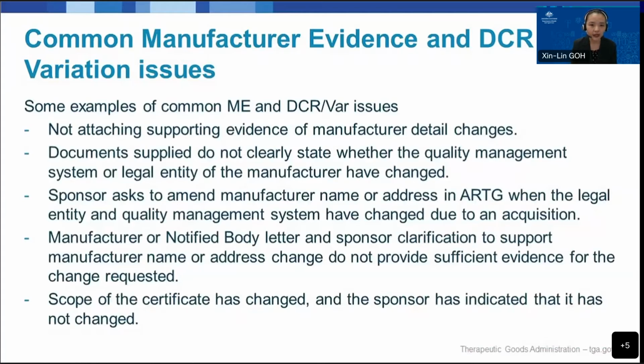So if the legal entity and quality management system has changed due to an acquisition, the new applications for inclusion will be required as it's considered a different kind of device. We've also had instances where sponsors indicate that the scope of the certificate has not changed, but upon inspection, the scope has changed. So just some things to take note of when preparing your applications.